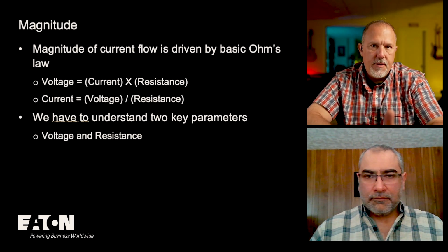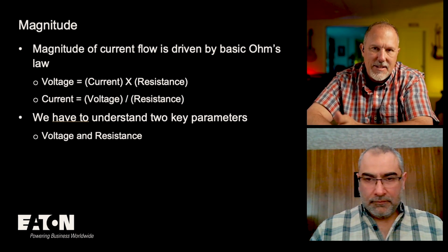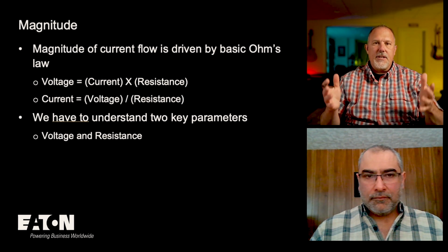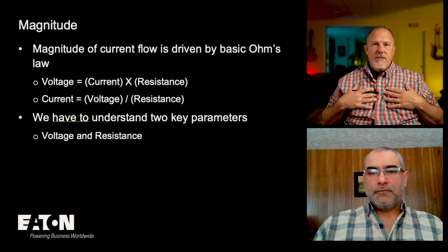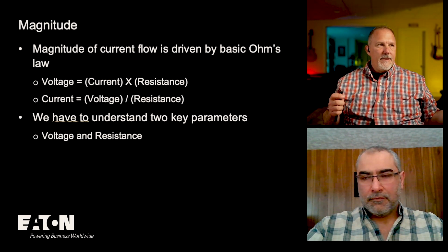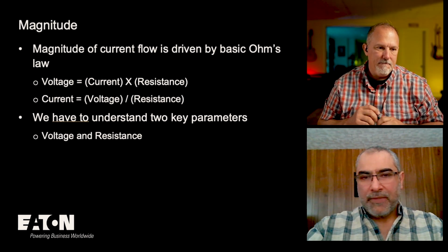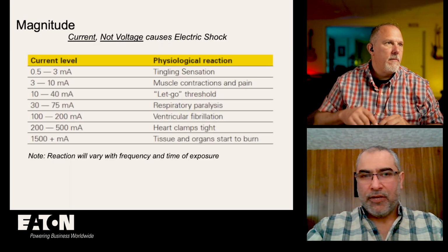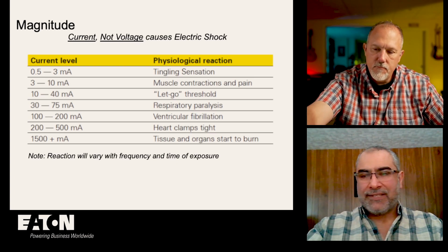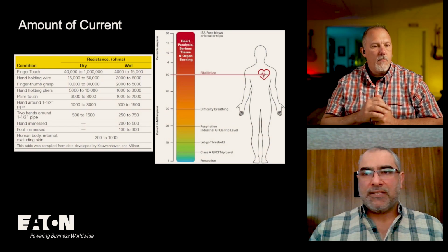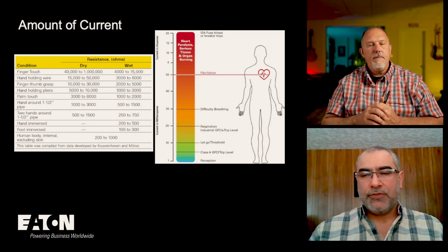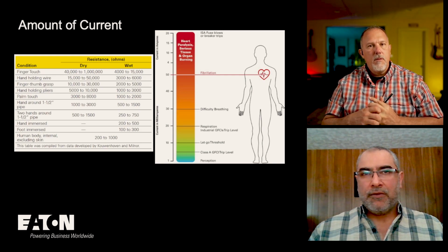So the magnitude of current, though, I can't control that necessarily either, because that's basically a circuit. The body has an impedance. The conductors have an impedance. And this is where the voltage comes into play, right? And the impedance of the body is not constant. It changes because of a lot of other factors. Like if there's any wet skin, moisture, it would put the resistance down. The voltage actually affects the resistance of the body, or the impedance of the body, I'd rather say, because it's not constant. It has a capacitive component, so it depends on frequency as well. We can't just assume that the impedance of the body is constant. It depends on the situation as well.